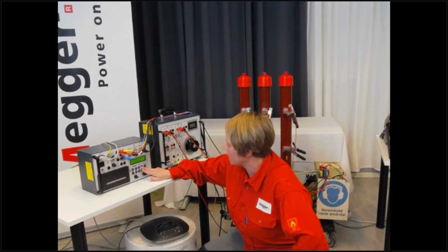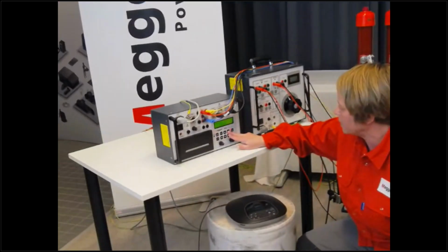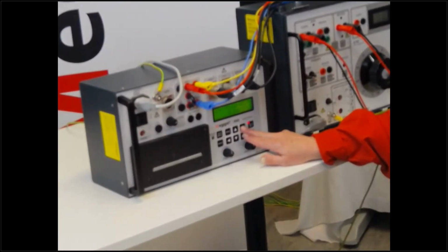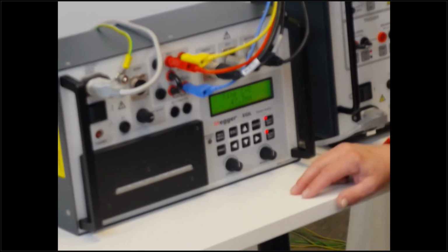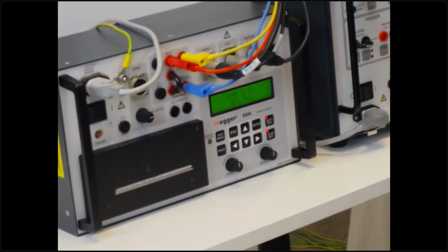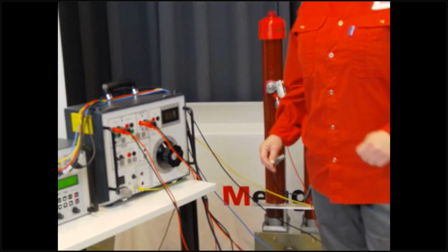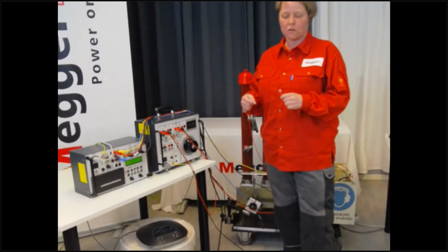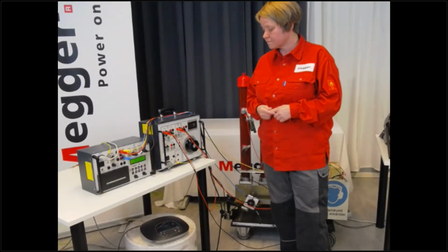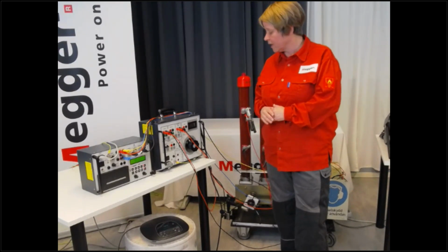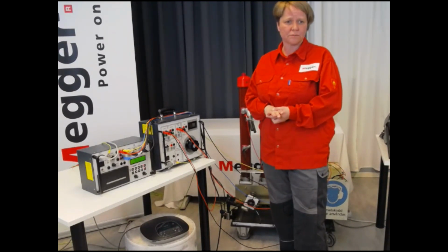And you get the different times, the close and the open, and the difference in similar ways. So by this test, you check that the circuit breaker is quick enough also when you have connected towards a fault. This was what I wanted to show you with Egil actually. Are there any questions regarding the demonstration? No?